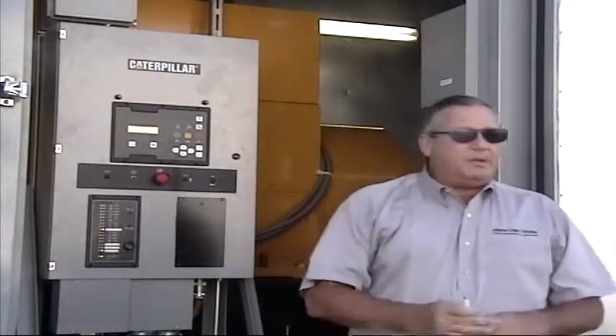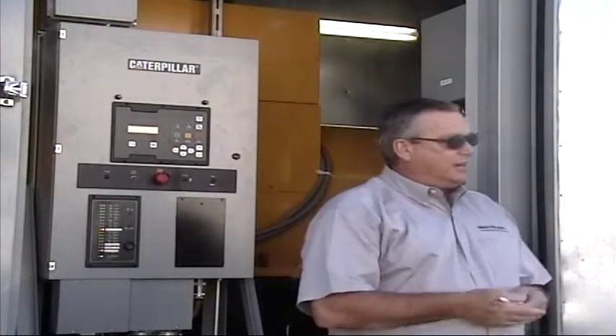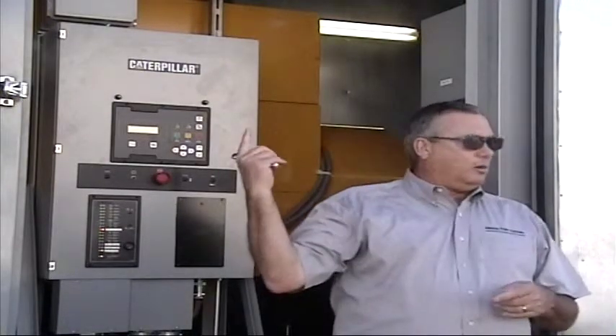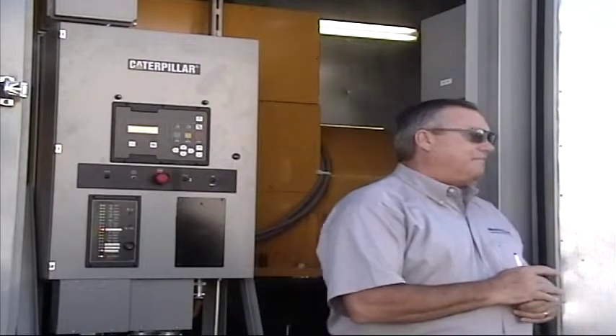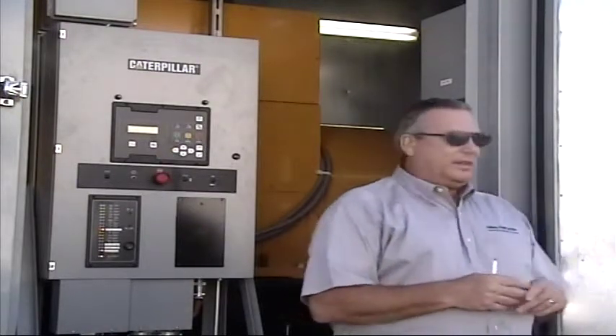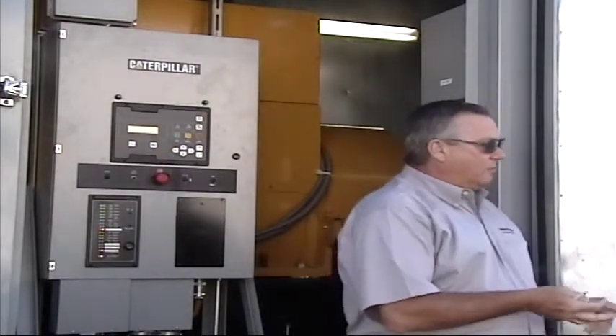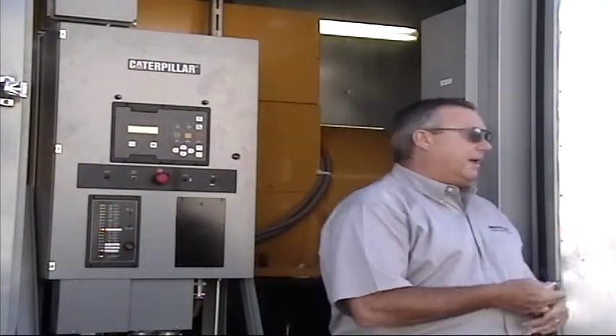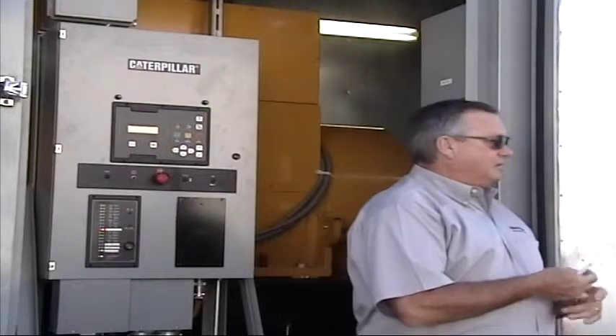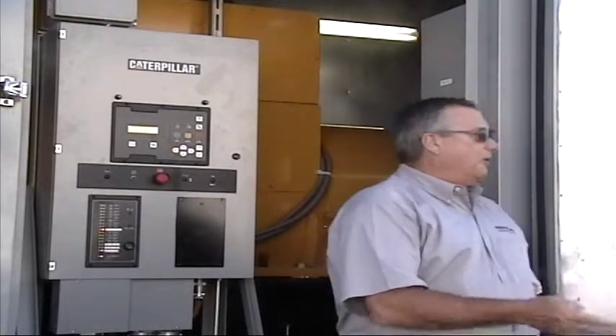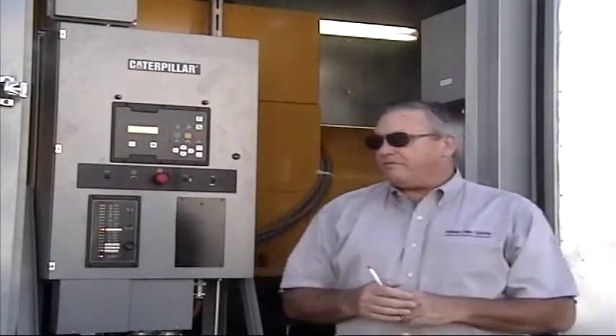Low coolant temperature is an alarm. If the coolant temperature drops below 70 degrees, we're going to get a low coolant temp alarm, and that probably means a couple of things: either the jacket water heater has quit working, or the breaker going to the jacket water heater has been tripped for some reason. We've got to figure out what that problem is. Once you get it back online, it'll heat the water up and that light will go back off.